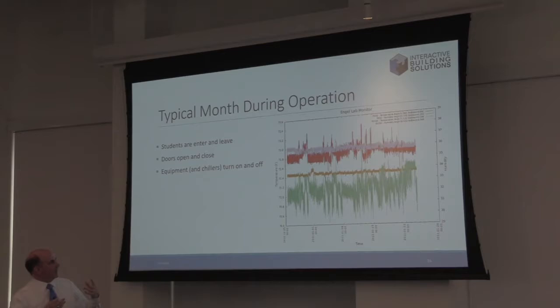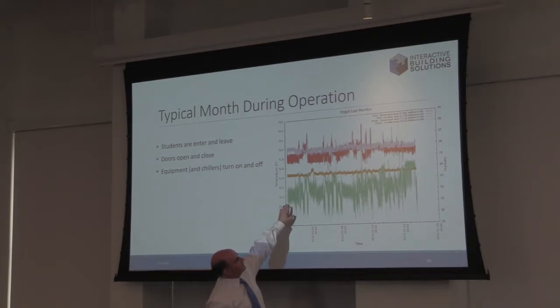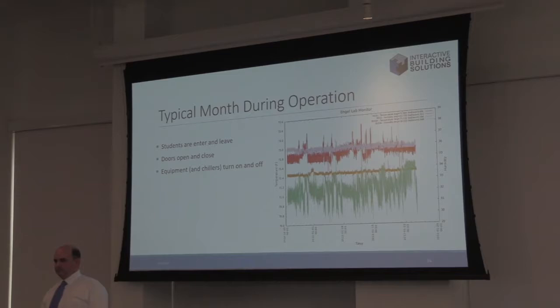And it causes some deviation from 71.8 almost up to 72, and then they shut it and things get better. But that lab's running well under 0.1 degree. The other one, the reason I was calling, this is what a disaster looks like. This is 0.2 degrees. Suddenly this lab that had been doing really well is about 0.2 degrees, and that's just way uncharacteristic. When things are running well, it looks much, much better.